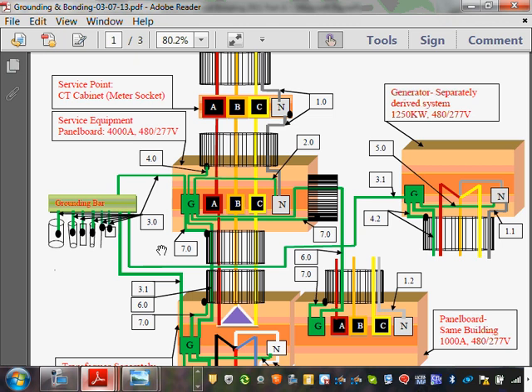We grounded the box, tied the box to the ground. We tied the neutral to the ground right at the service. Now, ladies and gentlemen, we're done with grounding and bonding at the service. You're done. That's grounding and bonding at the service panel. Any comments, any questions about grounding and bonding at the service?